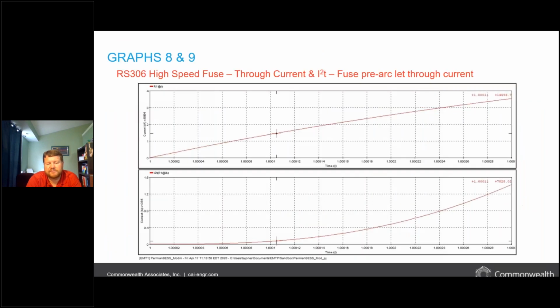So how do we deal with that? If the equipment is below its rating, how do we find a way to move forward? Well, the first issue would be to work with the equipment manufacturers to have them really look at testing their equipment to see if it can handle these high fault currents. Sometimes that's not even possible. To even generate these fault currents in a lab can be very, very challenging, even with our current testing equipment. So another method that we have is the use of current limiting fuses.